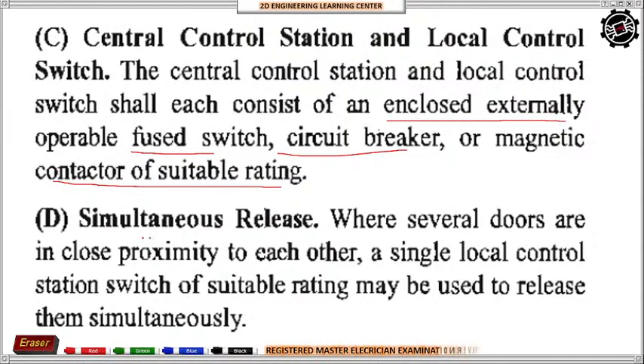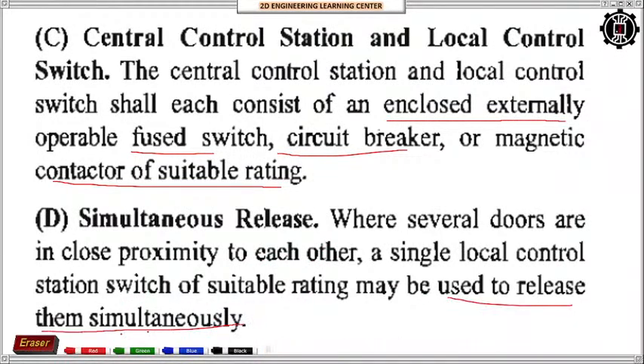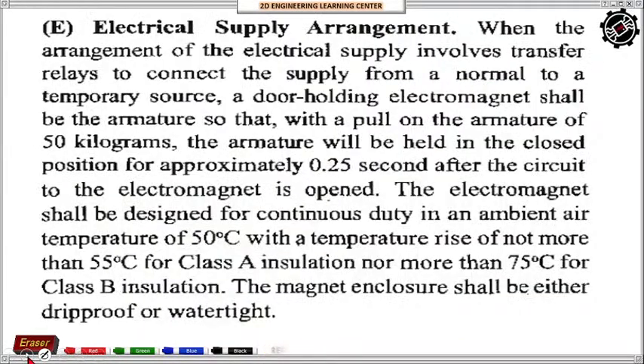In case of simultaneous release, where several doors are in close proximity to each other, a single local control station switch of suitable rating may be used to release all the doors simultaneously. So there is like a master release for simultaneous release.